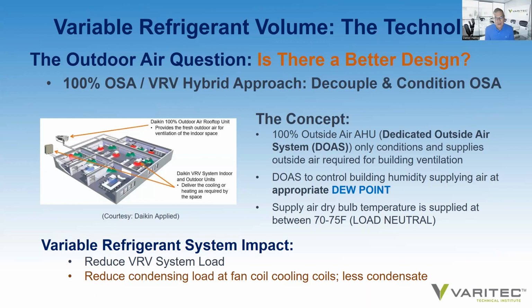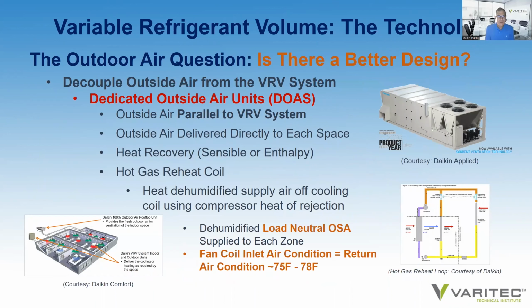So if you can handle the outside air through a DOAS unit, you reduce the VRV system load and consequently reduce the condensing load of a fan coil, the fan coil cooling loads, resulting in less condensate at your VRV fan coil unit. So decouple outside air from the VRV system using a dedicated outside air system. Again, to repeat, the outside air treatment through a DOAS unit is parallel and independent to the variable refrigerant system. Outside air is delivered directly and independently to each space, to each zone. You have enhanced energy efficiency by using heat recovery technology that is more often than not supplied with these units.